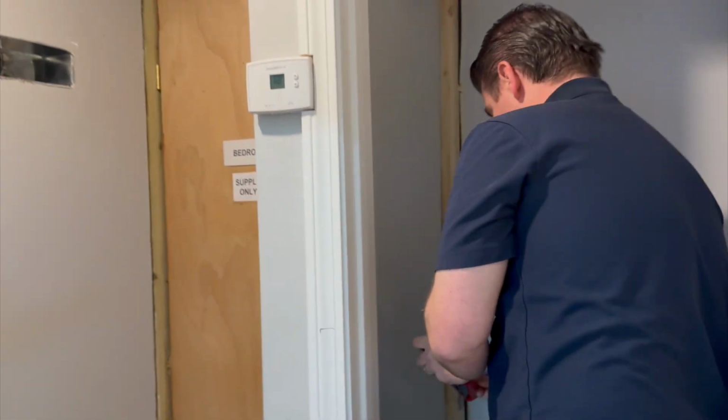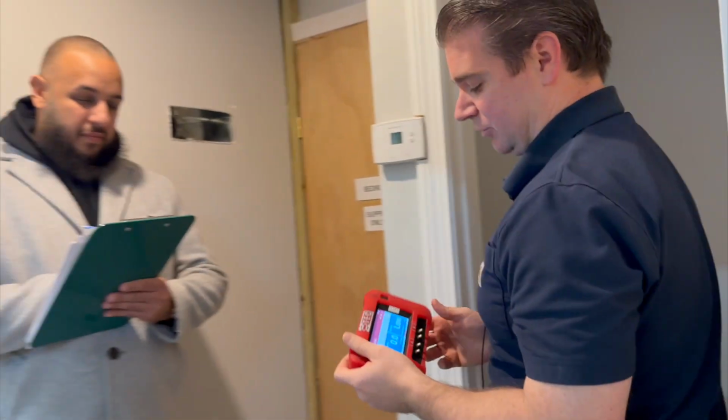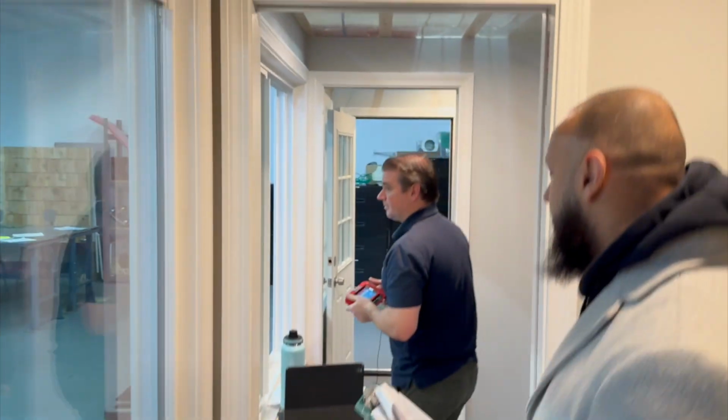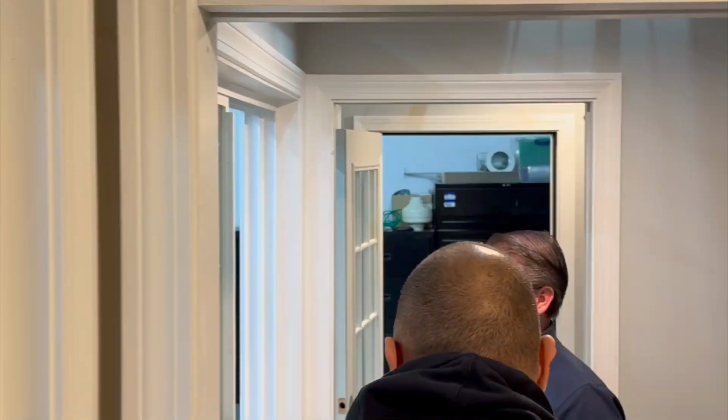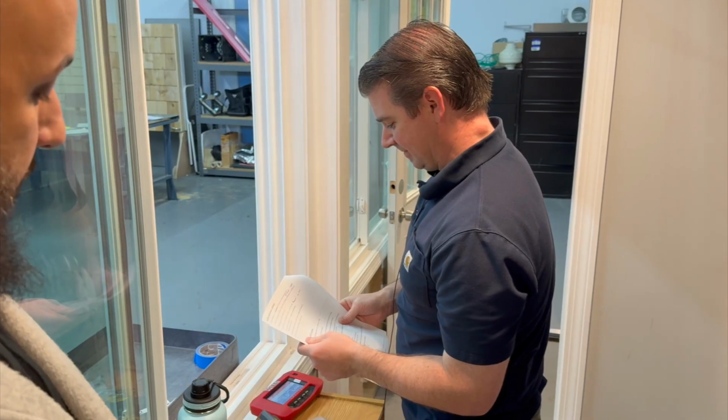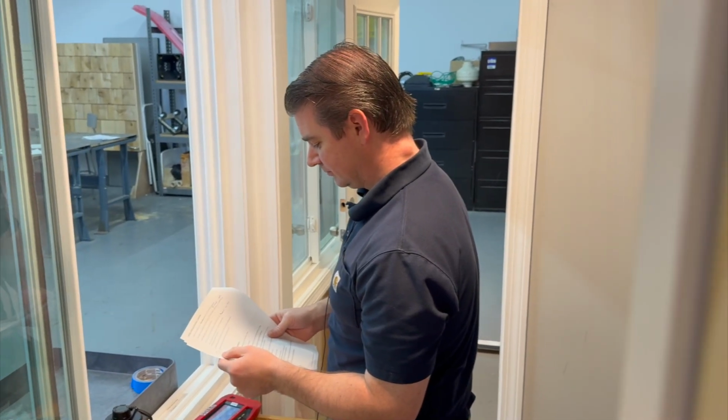I'll turn it back off. For bathrooms without a window, we want to have a minimum of 50 CFM fan installed. If it does have a window, we just need a minimum of 30 CFM. For a bathroom without a window, we want to have 50 CFM. Yeah, that would probably be best. All right, so that takes care of that section.